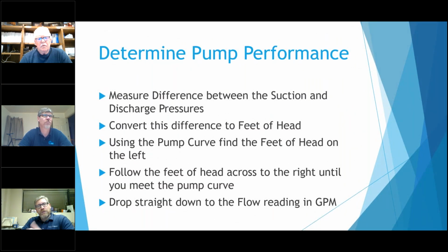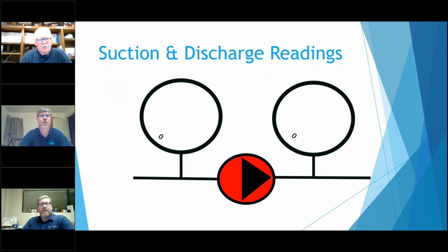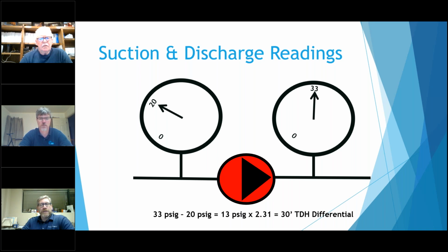But I do want to point out real quick this pump performance here. This is the wordy portion of it. Basically, you're taking a reading between the suction and discharge pressure, converting it to feet, and we're going to plot it on the curve and read the GPM from it. So a little graphic here. We've got a suction reading of 20, a discharge reading of 33. Convert that over. Do the math there. 33 minus 20. Convert it to feet. So we get a 30-foot differential.